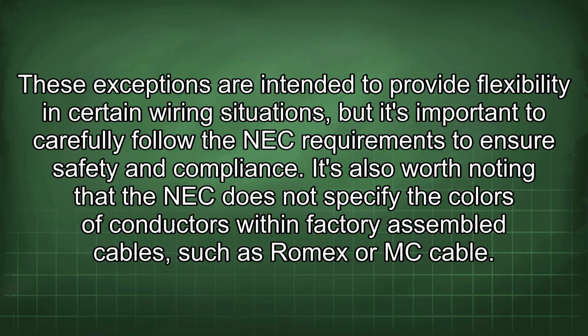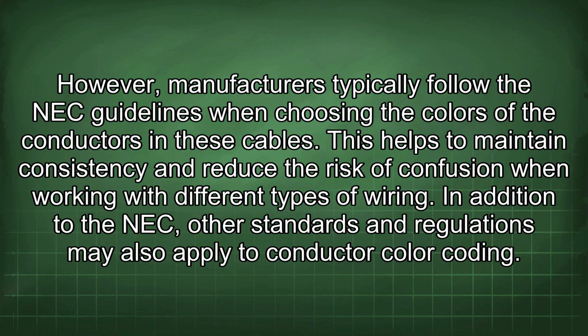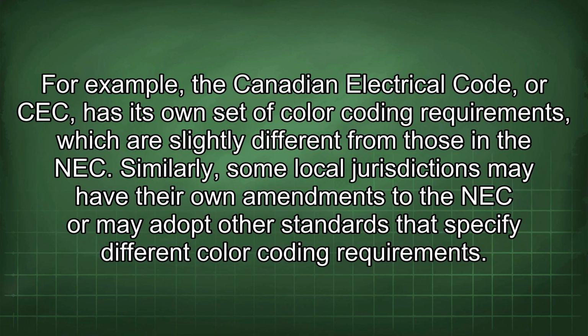It's also worth noting that the NEC does not specify the colors of conductors within factory-assembled cables such as Romex or MC cable. However, manufacturers typically follow the NEC guidelines when choosing the colors of the conductors in these cables. This helps to maintain consistency and reduce the risk of confusion when working with different types of wiring. In addition to the NEC, other standards and regulations may also apply to conductor color coding. For example, the Canadian Electrical Code, or CEC, has its own set of color coding requirements, which are slightly different from those in the NEC.